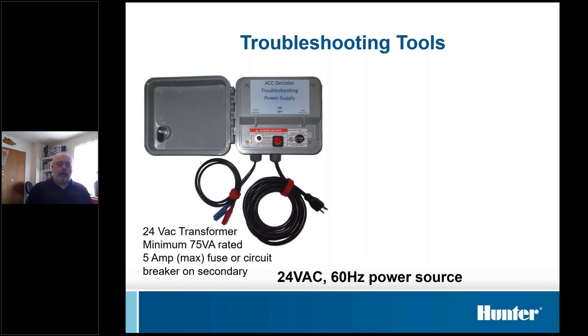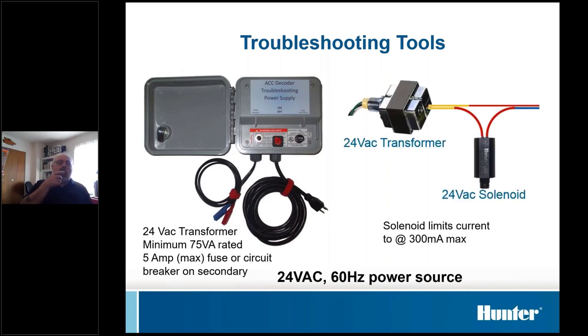But all it actually is, is a transformer. The one I use looks a little bit different than that. It's a transformer out of an ACC controller, which is a 75 VA or a 3 amp transformer. We put a 5 amp fuse, or circuit breakers better, on the output side, on the 24 volt side. We usually put a fuse on the incoming side. What we want to make sure is we don't blow the circuit breaker someplace where we don't know where to get at, where we don't know where the panel's at. And then otherwise, it's just a 24 volt power supply. We're going to hook this up to the two wire path and use the amp probe to find problems. This is just an alternate to that.